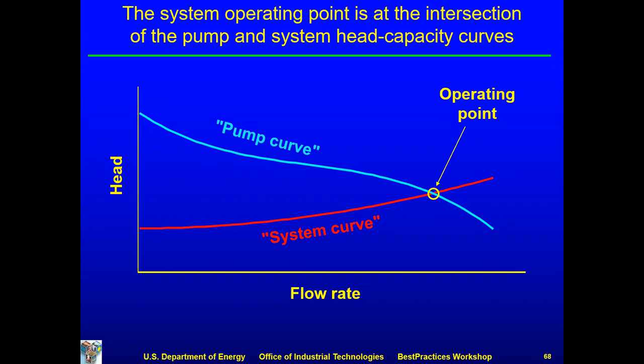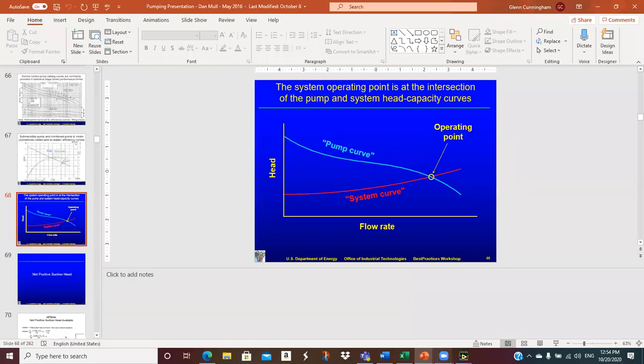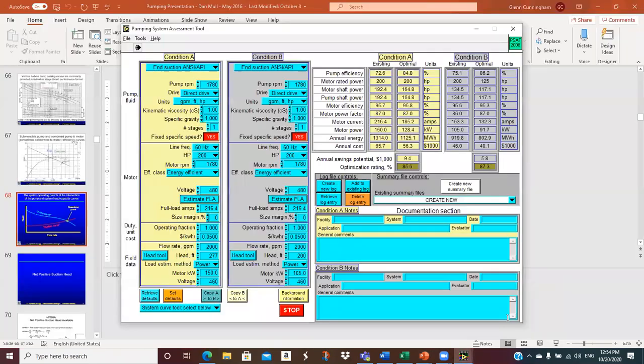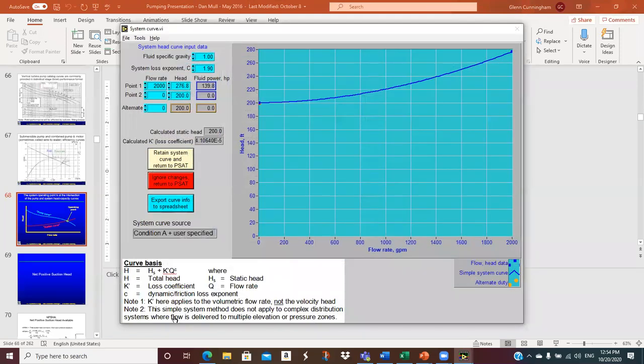So where does a pumping system operate? At the intersection of the pump curve and the system curve, where those 2 things come together. Oh, that's what I didn't show you on PSAT. I knew there was something else. We're going to have to go back. I'm getting forgetful in my old age. System curve tool. Oh, yeah. So this is a system curve calculator.